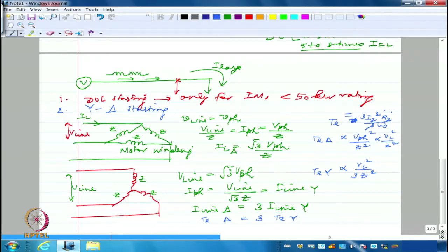Right? So the torque is also going to get decreased by a factor of 1/3. When I look at the delta, the torque will be much higher. So we are taking a hit on the torque generated by the machine, no doubt, but we are also reducing the current. So it's not a great option if I am trying to start an induction motor which is probably coupled to a hoist, an electric vehicle, or an elevator, because those things require a high starting torque. Whereas here the torque is going to be very, very limited. I'm not going to get a good amount of torque.